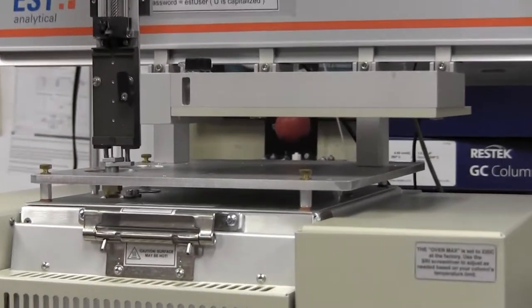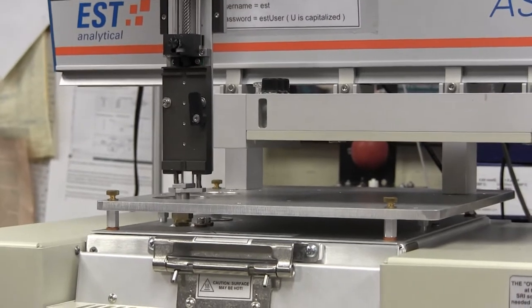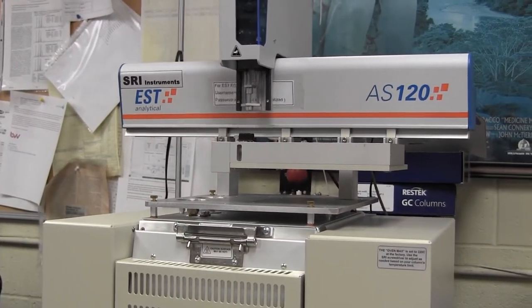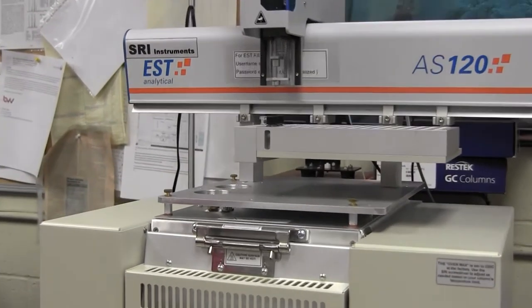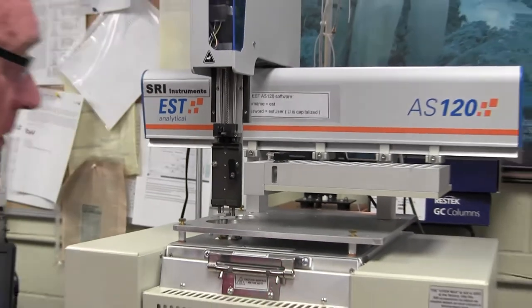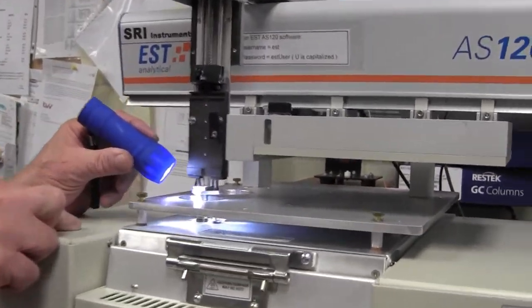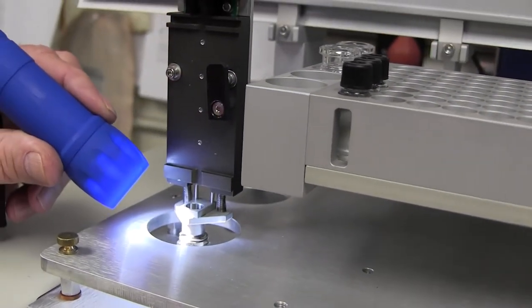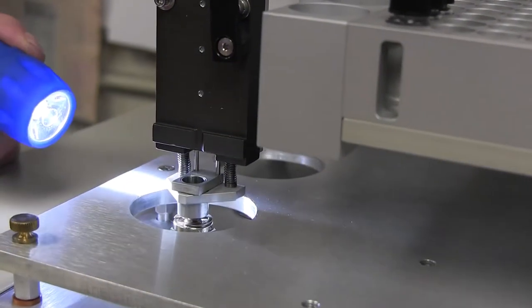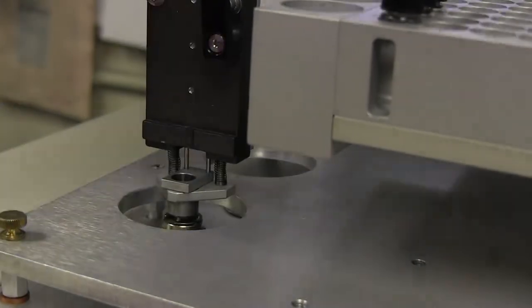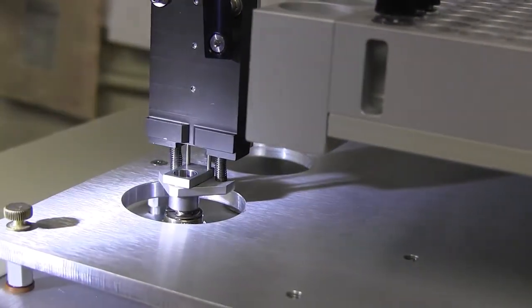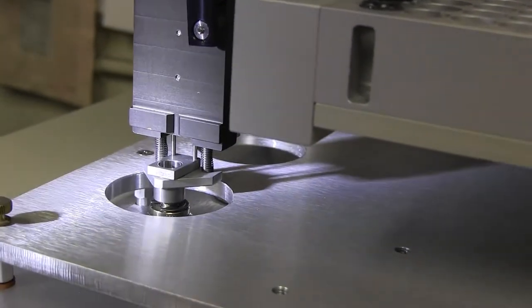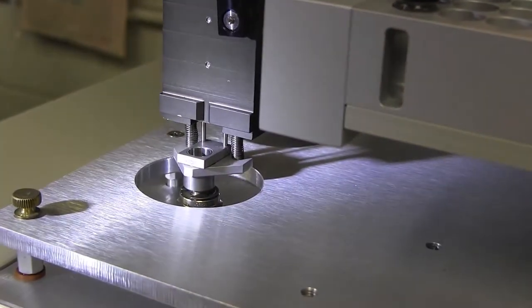So it's a good thing I did this. I'm going to go back to the home position and then I'm going to do that again and just make sure that it is aligned because it's supposed to go in that little hole right there. So I'm not sure if the video camera will be able to catch this because it's kind of a fine detail but the syringe has to go into a very small hole just really big enough to align. So it has to be pretty precisely aligned. So you have to look at this before you put the syringe in and make sure that it is because if you do this test with the syringe in there it's just going to break a $50 syringe. So we're trying to avoid doing that by making sure it's properly aligned before we put the syringe in because once we do we're at risk of damaging it if it's not aligned.